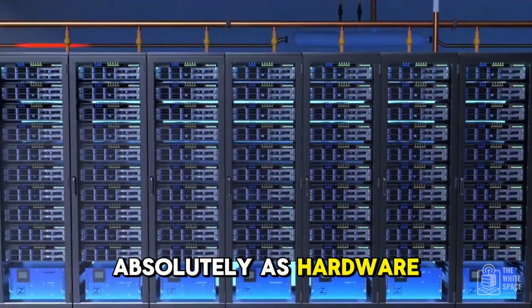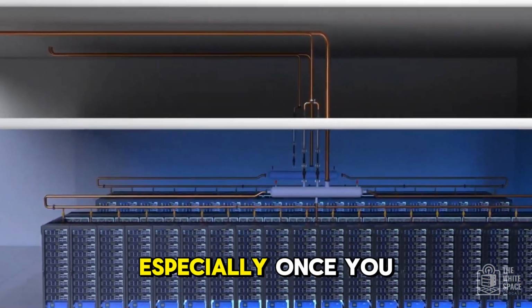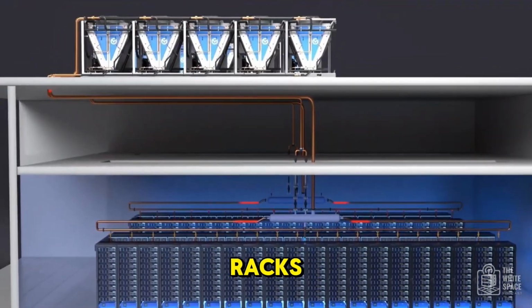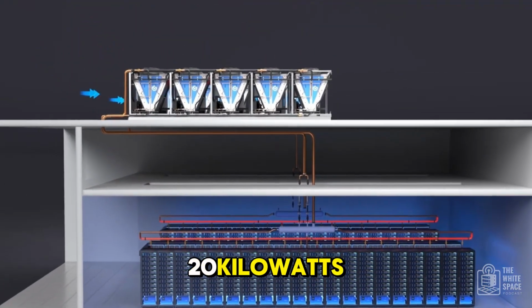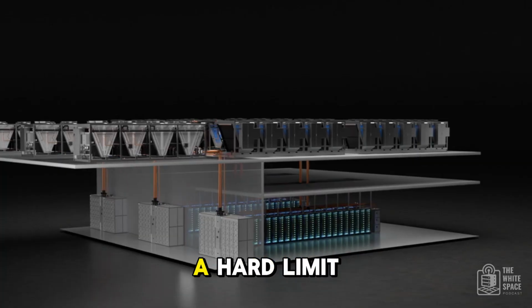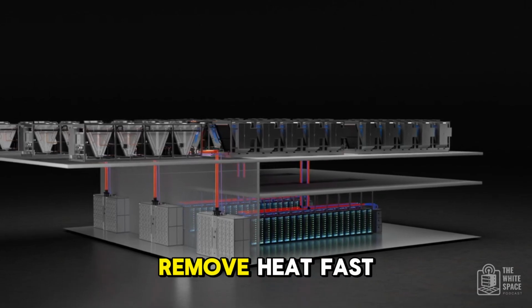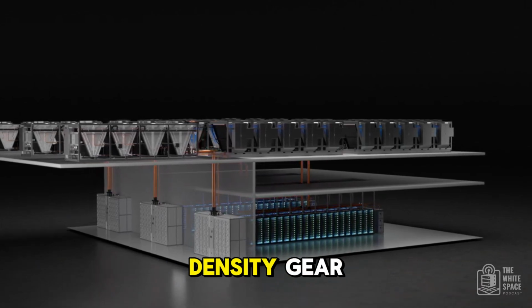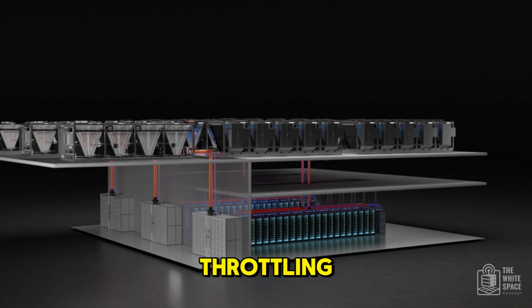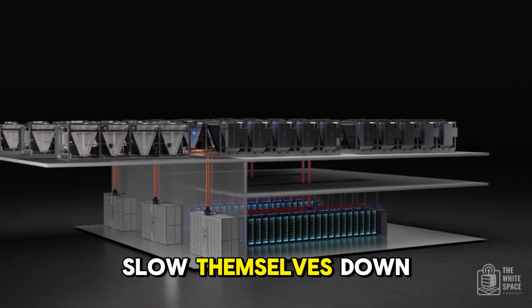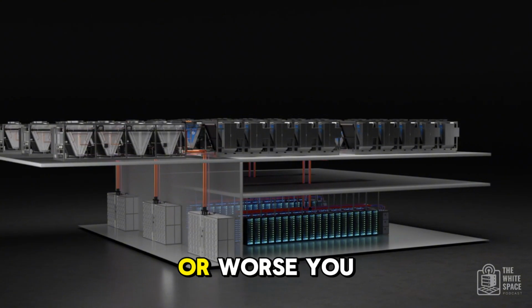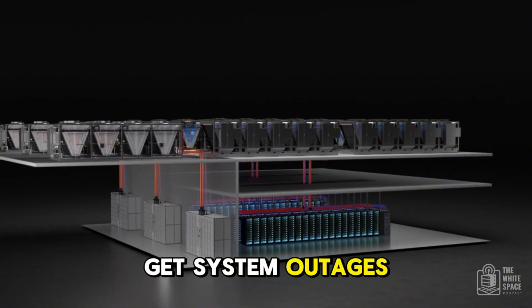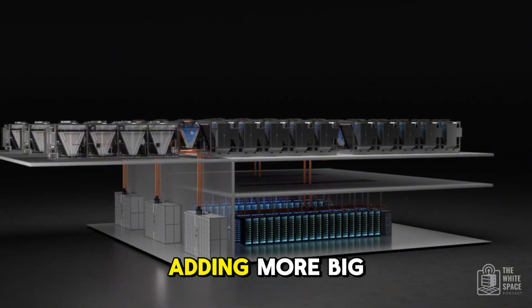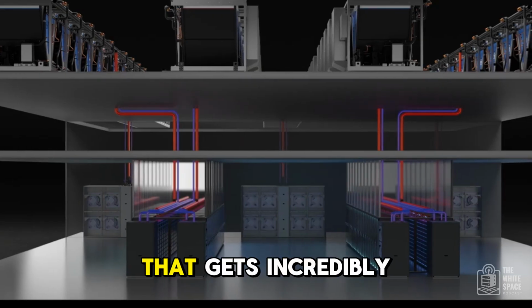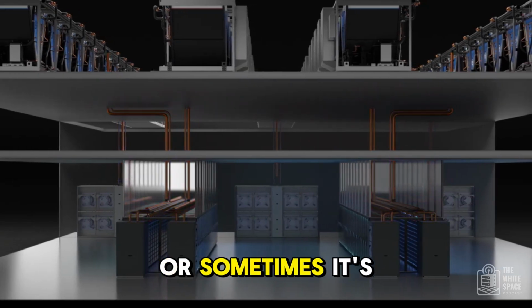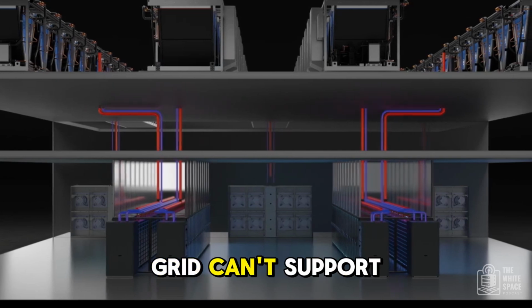Absolutely. As hardware gets faster and racks get denser, especially once you start talking about racks pulling over, say, 20 kilowatts of power, air cooling hits a hard limit. It just can't remove heat fast enough for today's high-density gear. This forces performance throttling—your expensive chips slow themselves down to avoid frying—or worse, you get system outages. Trying to fix it by adding more big AC units gets incredibly expensive, or sometimes it's just not feasible because the power grid can't support it.